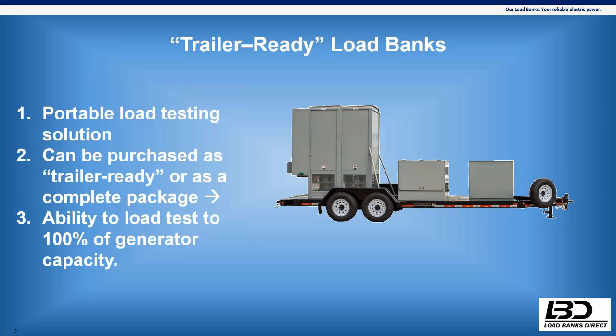That gives them the ability to load test to 100% of the generator capacity, whereas other styles of load bank can be limited to 50% or less. Being self-cooling gives them that ability, which depending on the application can be very important. Some people like to see a 30 to 50% load test, while other applications want to see the generator running at 100% load for maybe 2, 4, or even 8 hours. With a trailer ready load bank, you have the capability of hitting all those benchmarks when load testing.